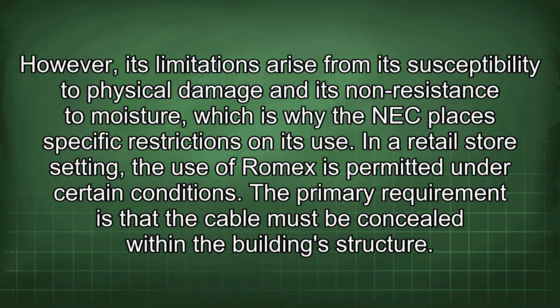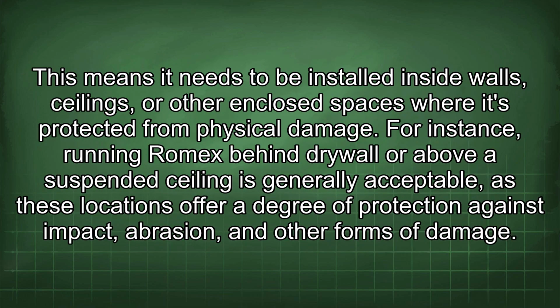In a retail store setting, the use of Romex is permitted under certain conditions. The primary requirement is that the cable must be concealed within the building's structure. This means it needs to be installed inside walls, ceilings, or other enclosed spaces where it's protected from physical damage. For instance, running Romex behind drywall or above a suspended ceiling is generally acceptable, as these locations offer a degree of protection against impact, abrasion, and other forms of damage.